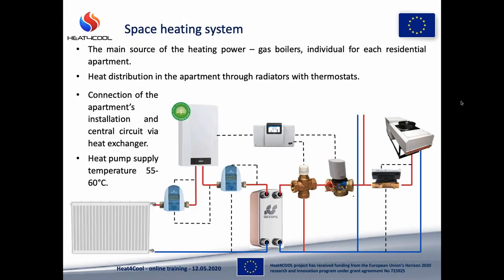Regarding the space heating system, we have 2 separate circuits in the building. In each apartment, next to the gas boiler, which, as it was mentioned, is the main heat source for each apartment, we have a heat exchanger installed. In this place, both loops are connected. And in the first circuit, which is between the heat pump and the heat exchanger, we have installed the heat meters to measure the heat provided to each apartment.